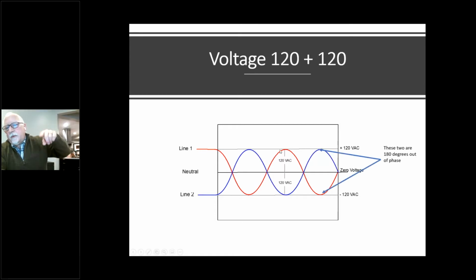And the amplitude of that wave is the actual voltage. So how high it is is the actual voltage. When you introduce a second line, it's a second 110, 120 volt line. But you can see that they're out of phase. So the red line and the blue line are actually 180 degrees out of each other. So when one is peaking, the other one is in the shallow.